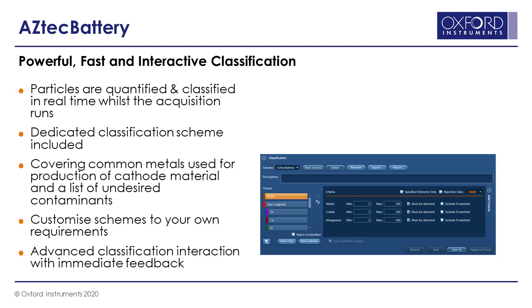Using the methods described, particles are rapidly identified and classified using a classification scheme set up around what is expected in the powder materials used in the battery industry. We can classify particles as cobalt oxide, manganese oxide, and so forth, covering the most common metals used in cathode material production or undesired contaminants — quickly determining what is an expected component versus an unexpected contaminant. The classification schemes can easily be customized for other applications.